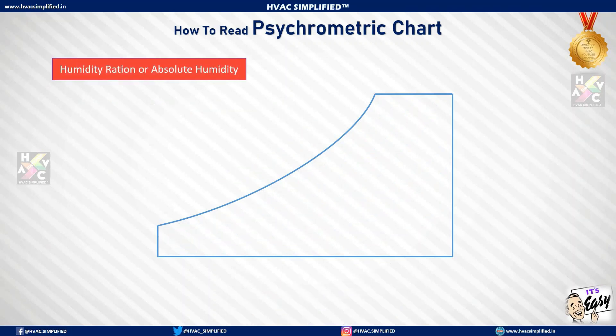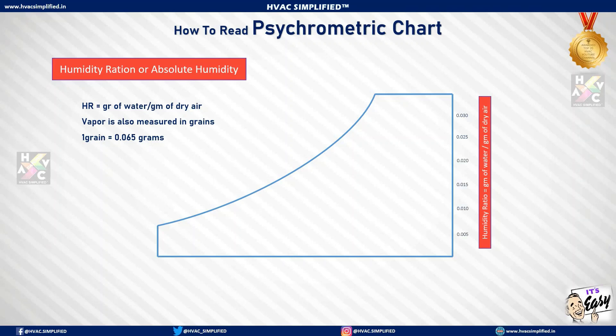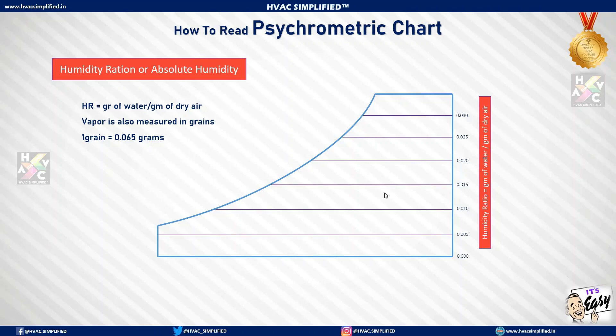The next parameter is humidity ratio, also known as absolute humidity. It is measured in grains of water per gram of dry air. Vapor content is also measured in grains, where one grain is equal to 0.065 grams. On the psychrometric chart, the humidity ratio is shown on the right-hand side and is read using horizontal lines.